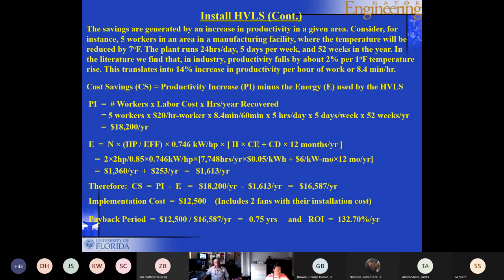This is known, and we have cited a source for that. That translates into 2%, translates into 14% increase in productivity per hour of work, or in this case, 8.4 minutes per hour. And therefore, if you want to compute the cost savings, it would be the productivity increase minus the energy that has been used to run these high volume, low speed fans.